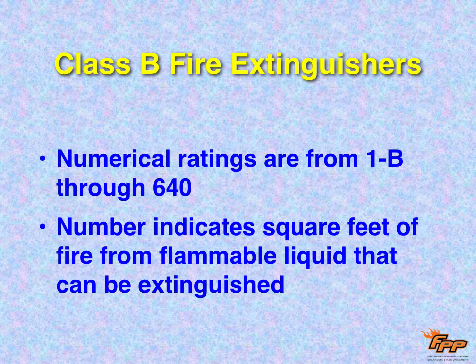Class B fire extinguishers are for flammable liquids, Class B fires. So the numbers are going to indicate the square footage of area of flammable liquid that can be extinguished with that type of extinguisher. So a lot of times when you have your combo extinguishers, it'll say 2A 10BC. And that has to do with the area it can put out if it's an A, or the 10 would have to do with the square footage of the fire with flammable liquids that it could extinguish.